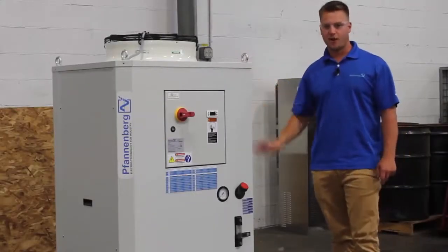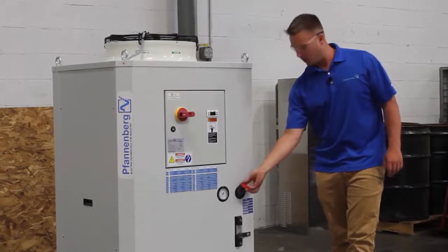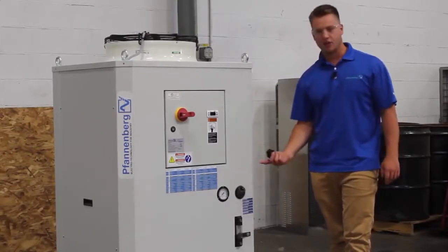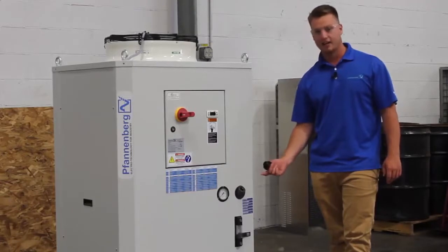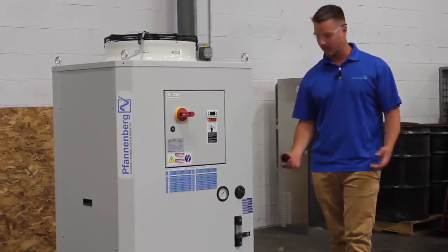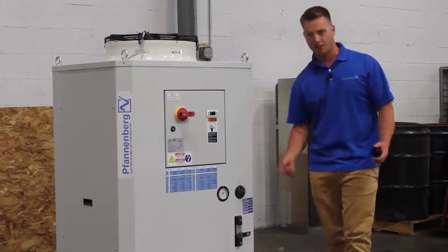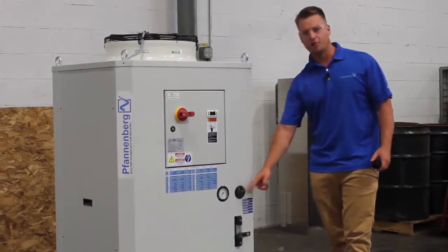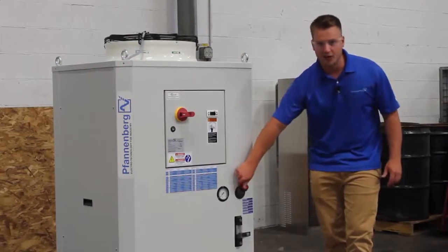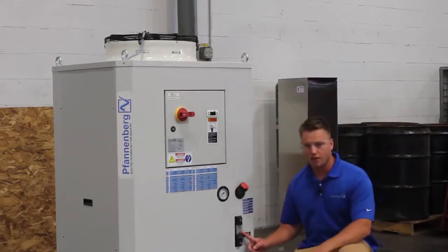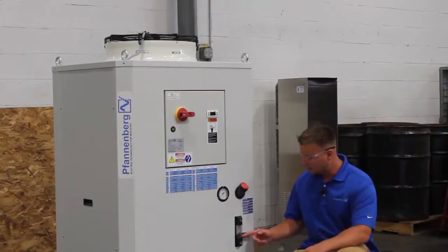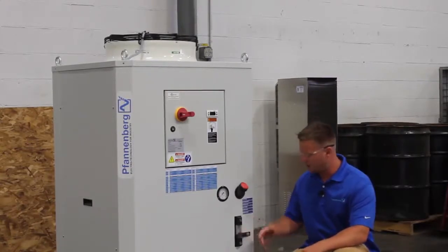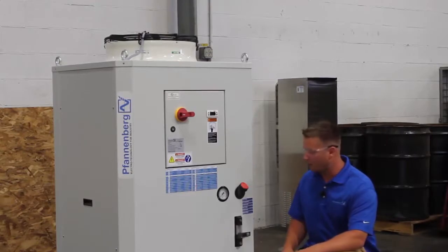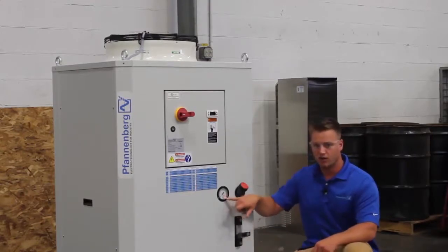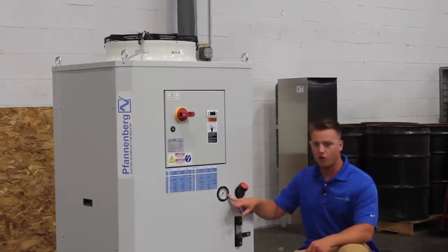One of the first features I want to point out is the fluid fill feature. Right here, we have a fill tube that goes right to our tank. It's similar to filling your car's gas tank. All you have to do is take your glycol water mixture and fill up the tank. As you're filling it, you'll notice that there is a gauge right here that'll show you the level that you're at. You simply fill it to the level you need to be at, and the chiller will be good to go. During operating, there's also a gauge here that'll show you what bar your chiller is operating to. That's great, so you know the head pressure of the pump.